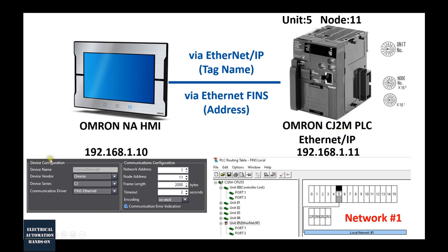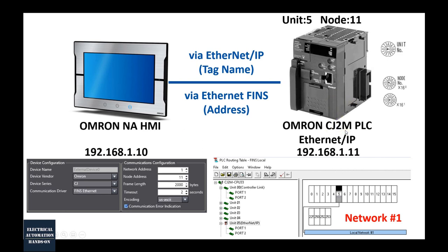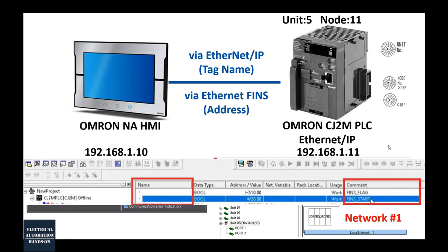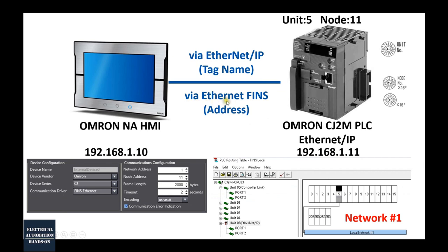The key issue comes from the HMI settings. This HMI has two ways to connect to the CJ2M. One is via the EtherNet/IP communication driver, and the other is via the older Omron-specific protocol called FINS — specifically Ethernet FINS. Because this project was upgraded from a CJ1M, I basically kept the existing program and symbols, which use absolute addresses. When I tried to set up the EtherNet/IP communication, I got into trouble, and then I realized I should use the Ethernet FINS communication.